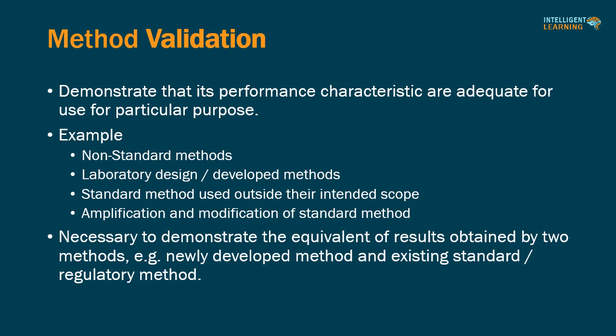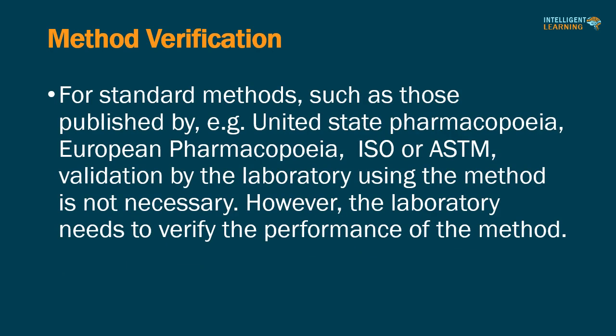Validation is also required when it is necessary to demonstrate the equivalence of results obtained by two methods — for example, a newly developed method and an existing standard or regulatory method. For standard methods published by organizations such as the United States Pharmacopoeia, European Pharmacopoeia, ISO, or ASTM, validation by the laboratory using the method is not necessary. However, the laboratory needs to verify the performance of the method.